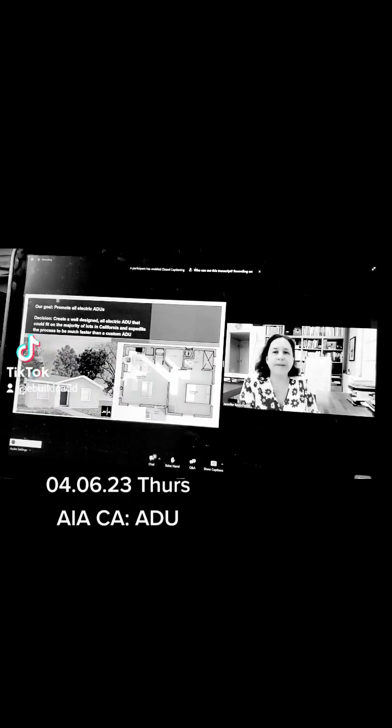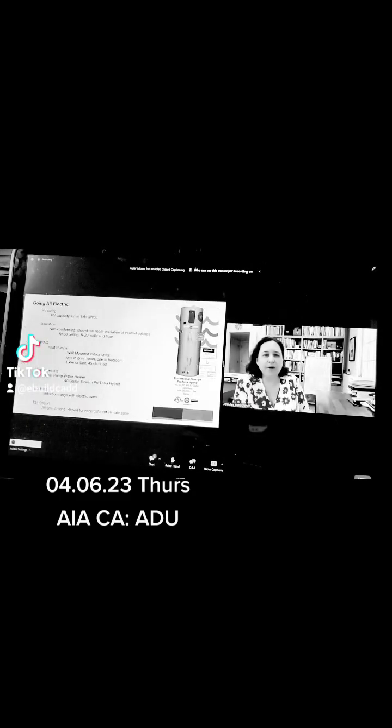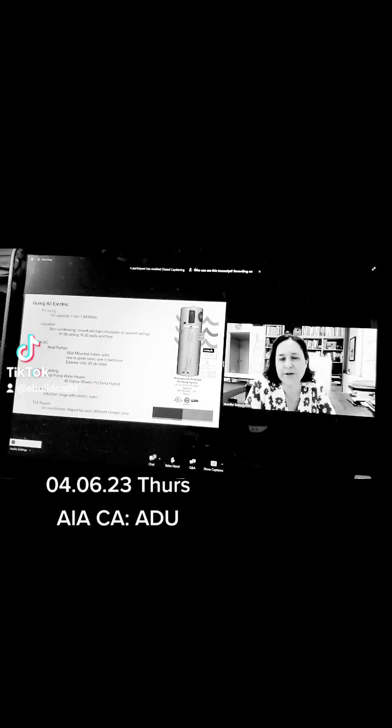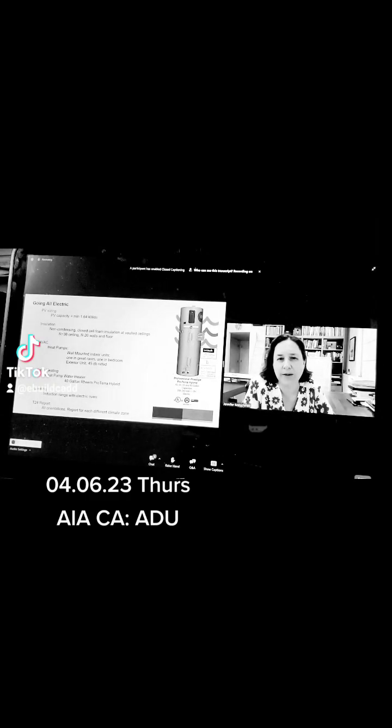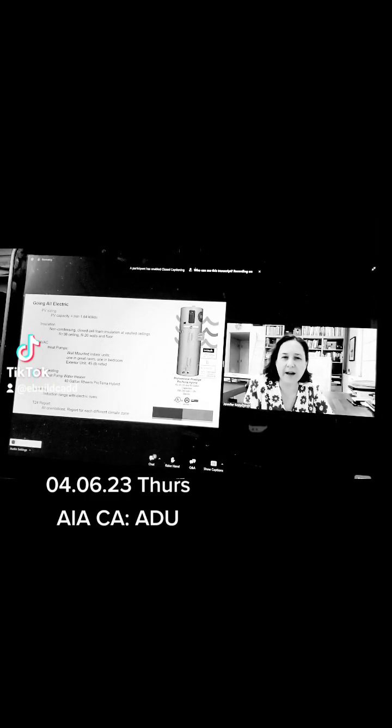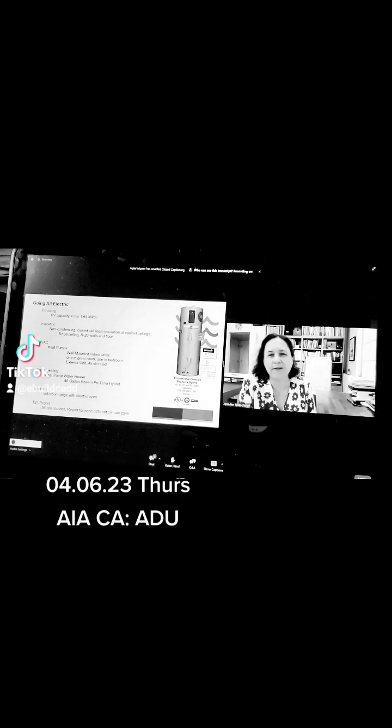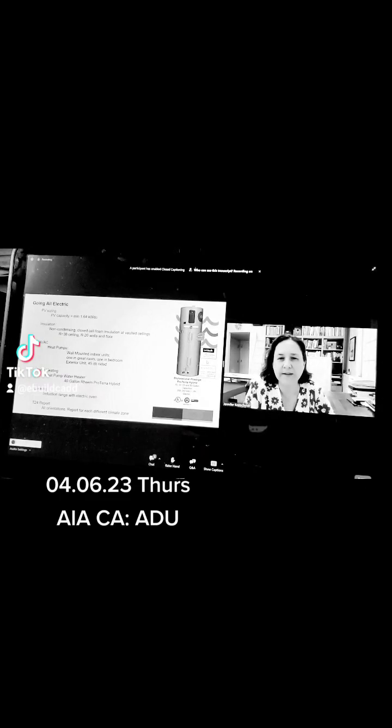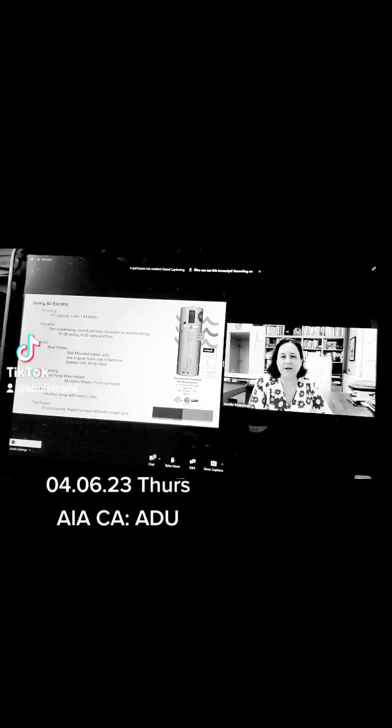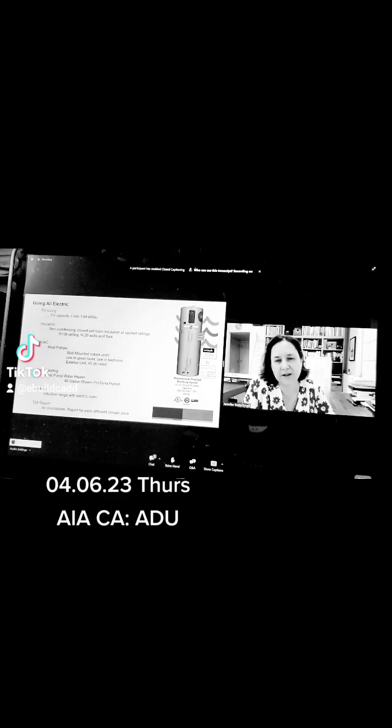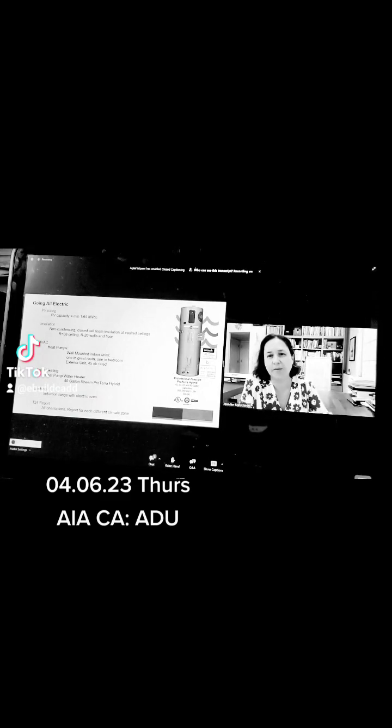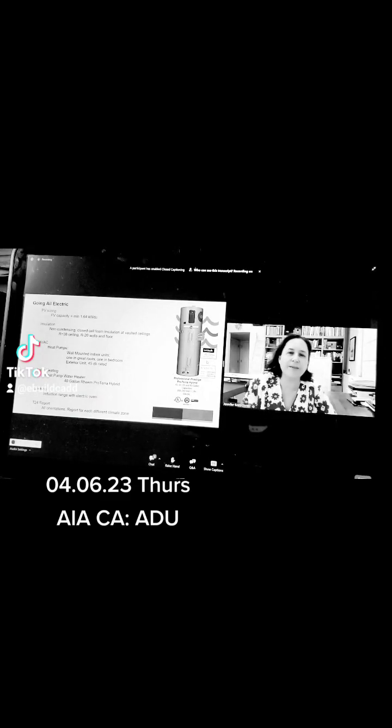Part of being able to go all-electric is including things, and some of this is from the 2019 code, so some of this will now change, including PVs, which for this particular ADU was 1.64 kilowatts DC. Insulating and creating high-vaulted ceilings, slope ceilings, so that this tiny space feels a little bigger. We're using heat pump water heaters and HVAC heat pump, typical mini-splits, including induction ranges with electric ovens. To make it work pretty much on any property, the Title 24 report is done for all orientations, and then we do have to do a separate report when there's a different climate zone.